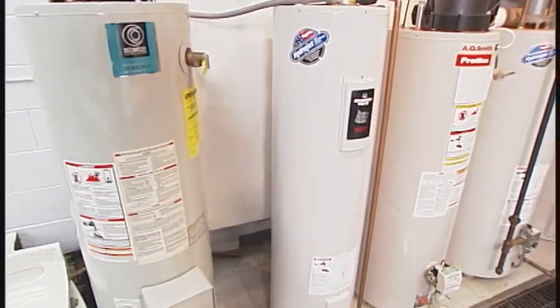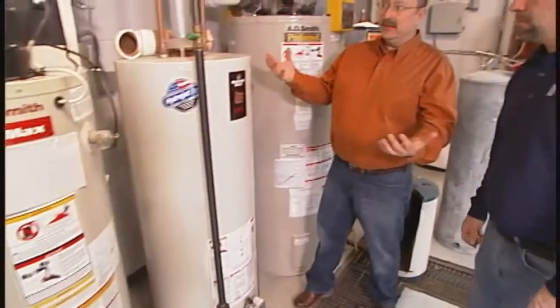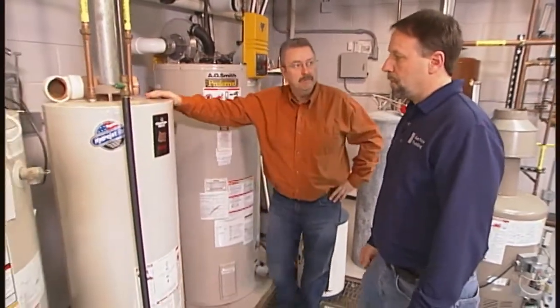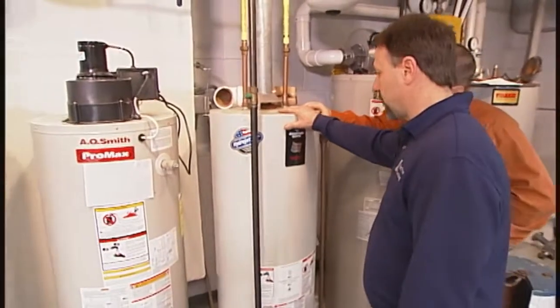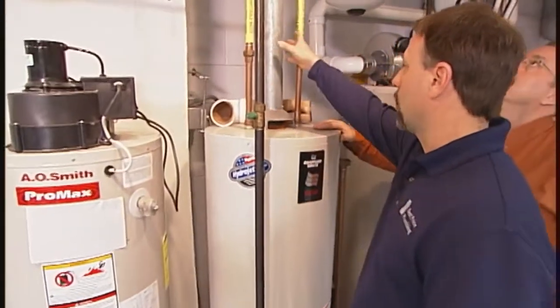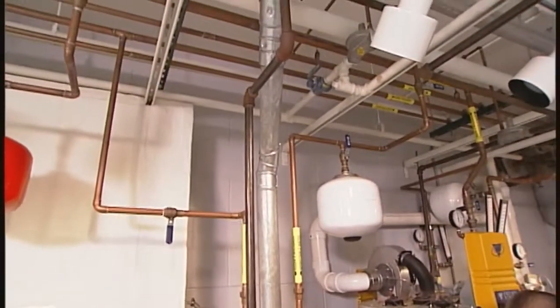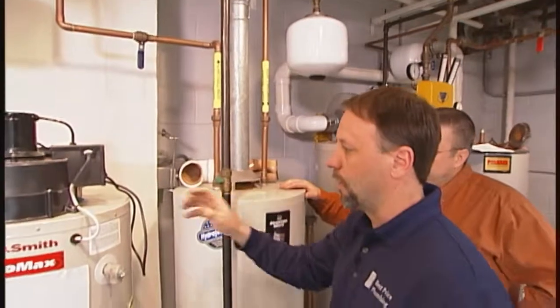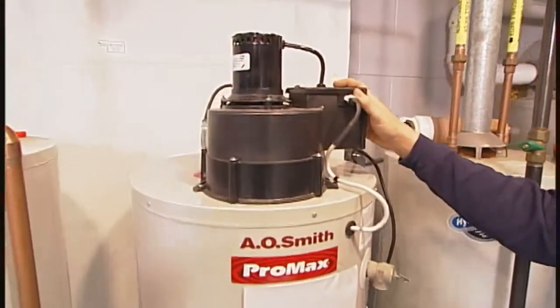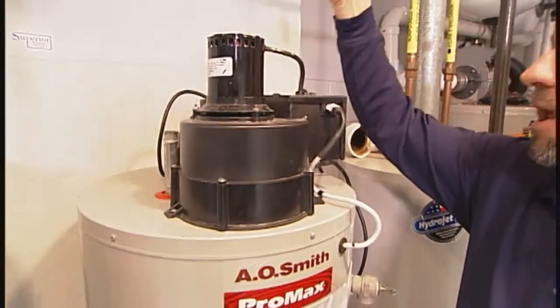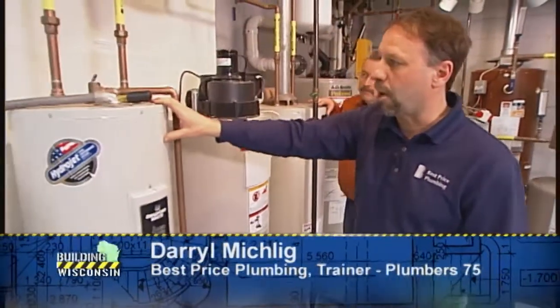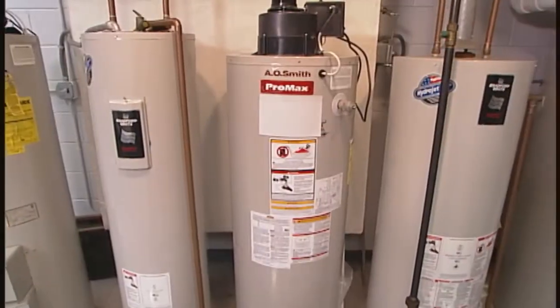You know, Daryl, there are a number of different ways of heating water in a home. Here at the training center, we have an opportunity to look at some of the different makes and models of water heaters that a plumber or a homeowner might encounter. So let's take this opportunity in Plumbing 101 to explain how they operate and provide some safety tips for a homeowner. On this case right here, we have a B-vent gas water heater, which means that this vent goes all the way up through and out your roof. So on this particular model, you need to vent it all the way out the roof. If you have a power vent water heater, like this one, you're going to have a blower motor on top that takes the gases and sends them through a PVC pipe out the side of your house. An electric water heater has no venting at all; it just has electric elements on it. So there are different types to be aware of out there.